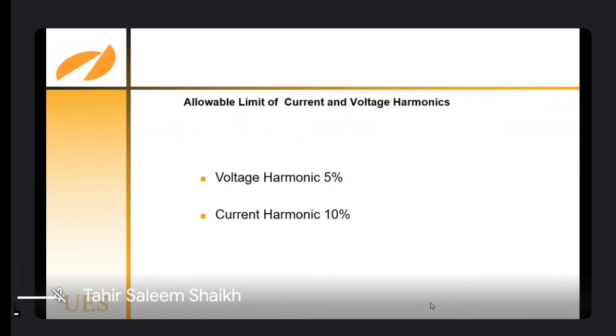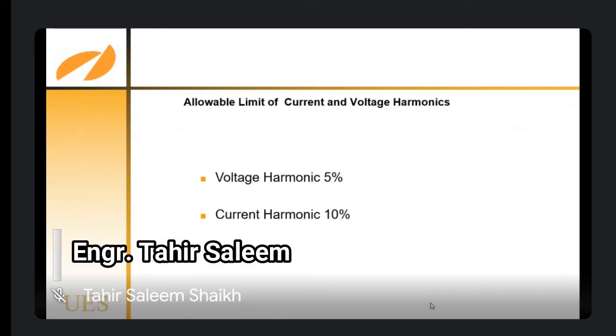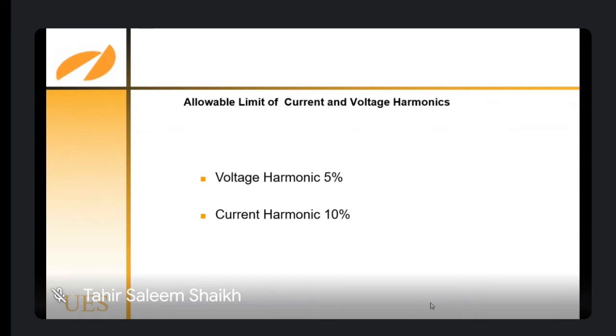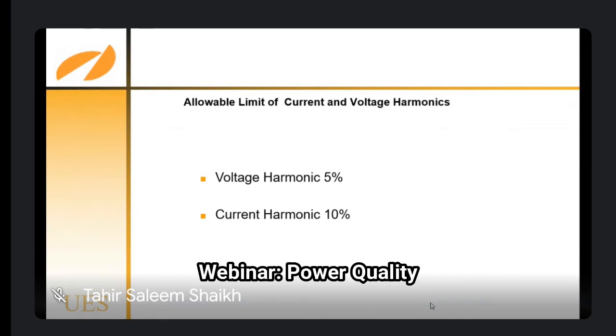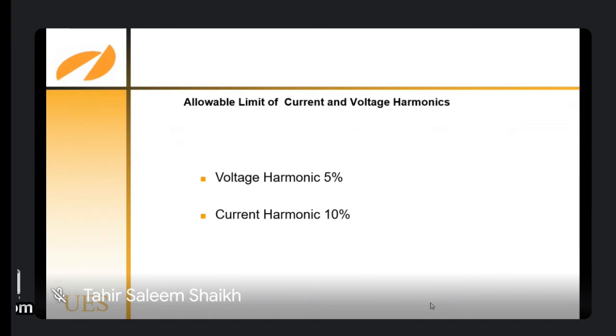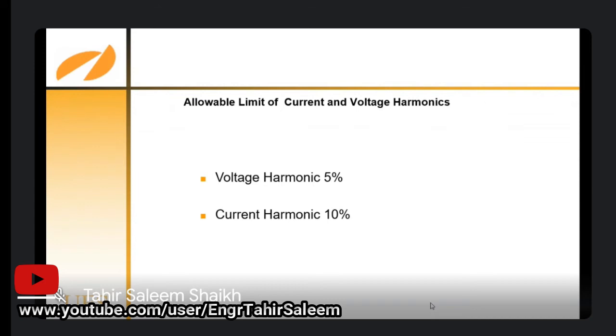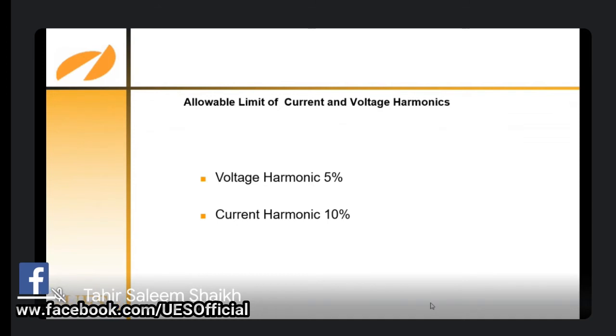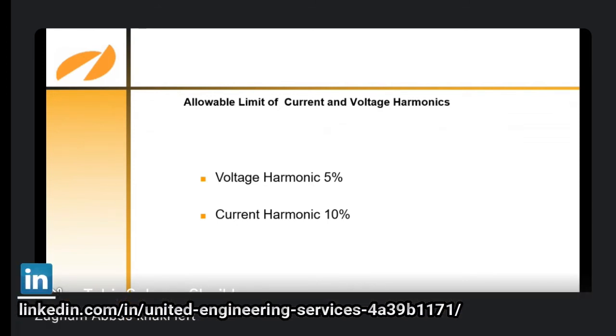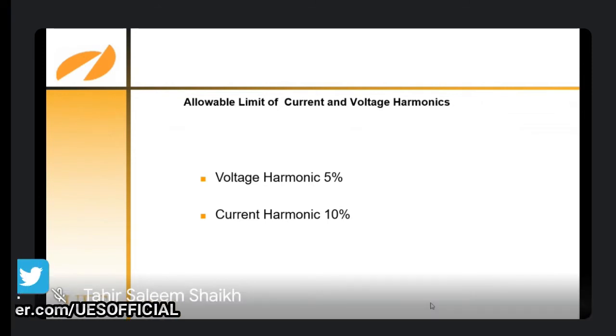The higher the source impedance, the more voltage distortion. In general, many multinational companies have set the voltage harmonics limit globally to 5% and current harmonics to 10%. But I have shown you the standard. For critical cases, you have to decide on the environment in which your equipment is working, and decide according to the standards, which vary from 3% to 8%. This has to be decided by yourself, because the generator doesn't create harmonics. The harmonics are created at the consumer end, and the consumer has to decide what to do.